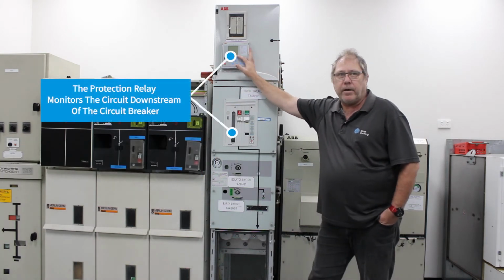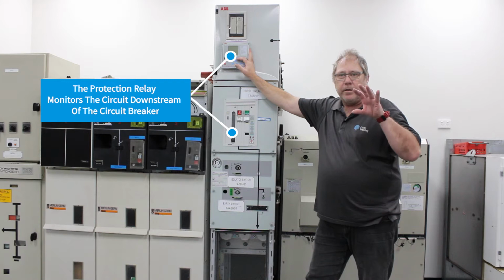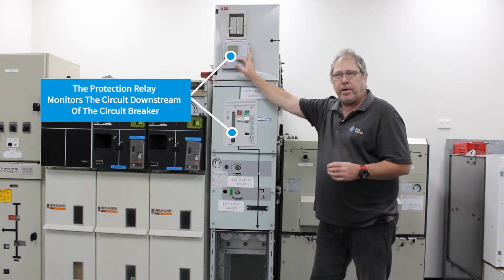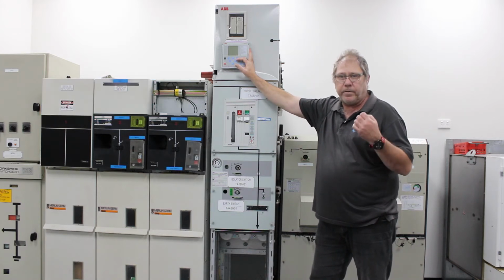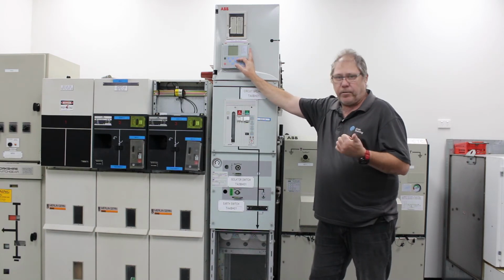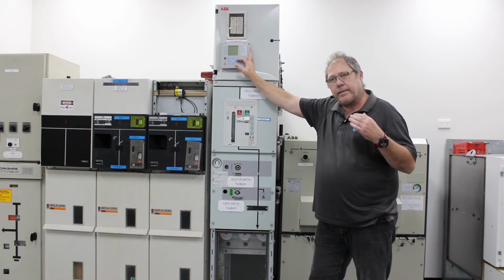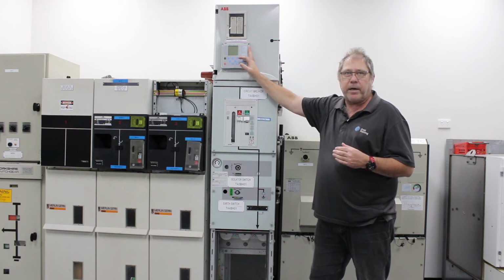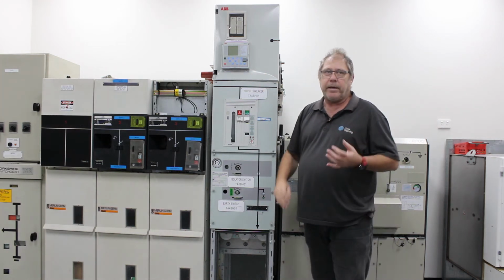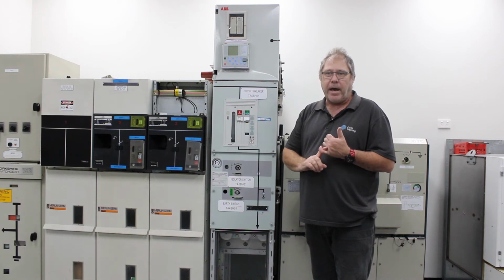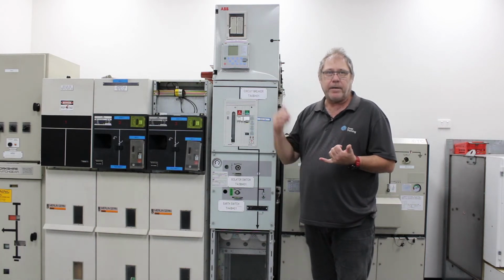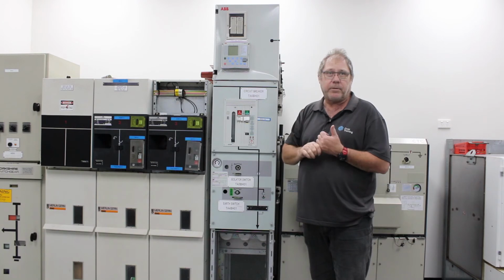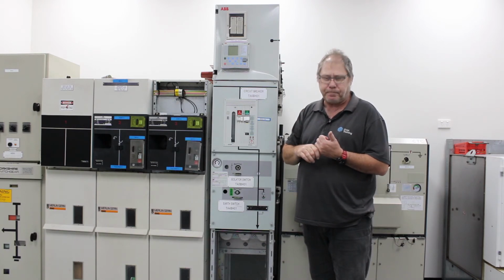The job of the protection relay is to monitor the circuit downstream of the circuit breaker through the use of current transformers and voltage transformers. The current transformers are an important component, as this gives feedback to the protection relay, showing the relay the amount of current flowing, and if there is an overcurrent, the program inside the protection relay can act accordingly.